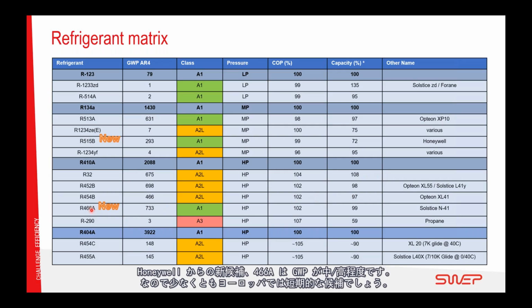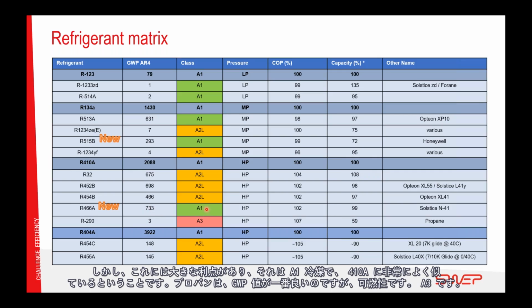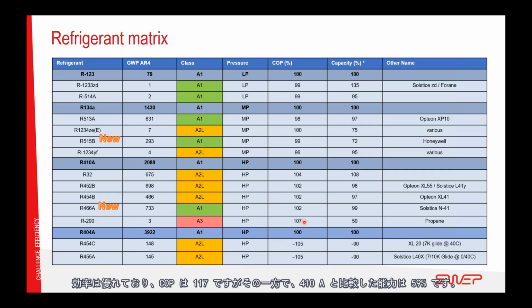The new candidate from Honeywell, R466A, has medium-high GWP, so it's a short-term candidate, at least in Europe, but it has the big advantage of being an A1 refrigerant, very similar properties to R410A. Propane, the best GWP of them all. However, it's flammable. It's an A3. It has excellent efficiency, 107 in COP, while only 59% of capacity compared with R410A.